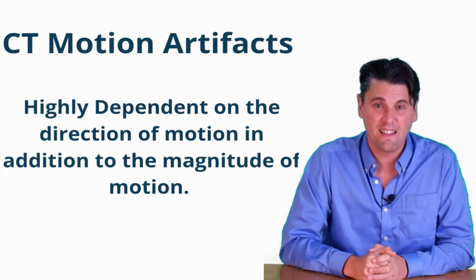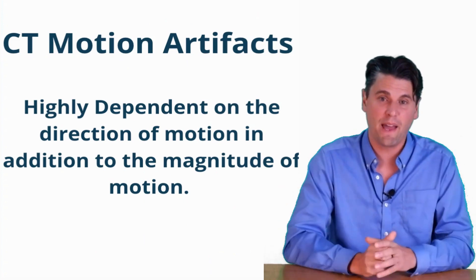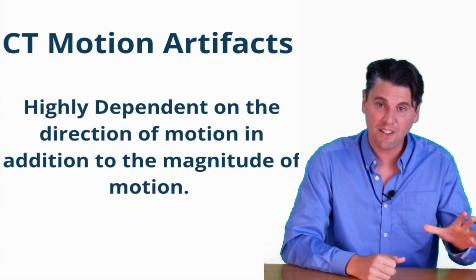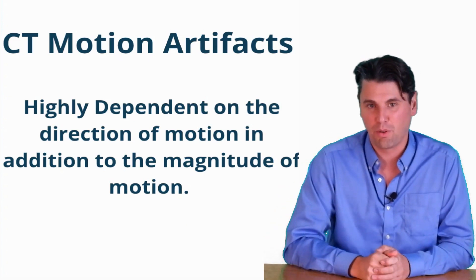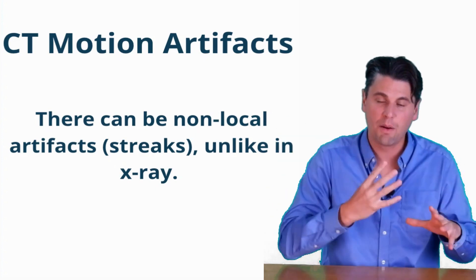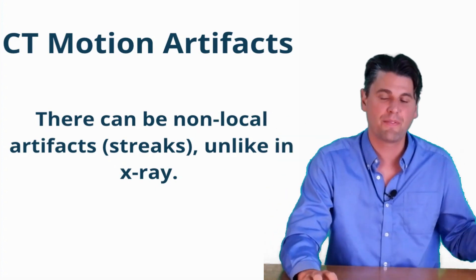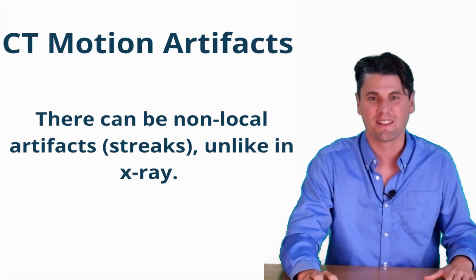So what really matters is actually motion that is perpendicular to the direction that the x-rays are acquired in. Those are the types of motion that will actually generate really significant artifacts, whereas this type of motion, if you back project this small level of difference, you won't really notice it in the image volume. Just a takeaway is that the CT motion artifacts are highly dependent on the direction of the motion in addition to the magnitude of the motion. These artifacts are also non-local, so you can end up with streaks in the images, which is different than in the case of just x-ray imaging.